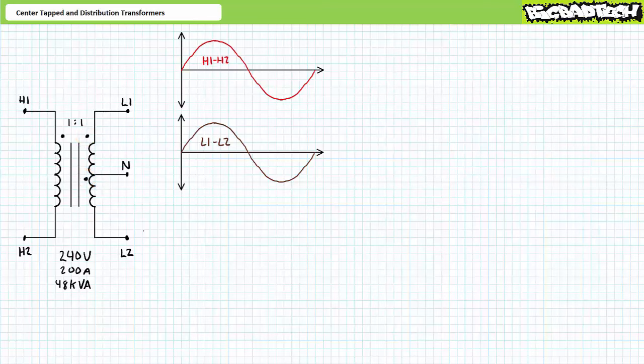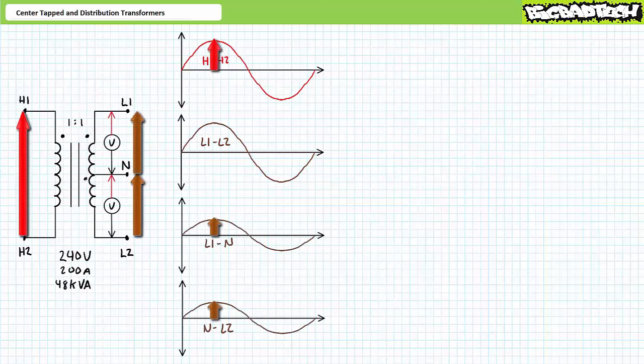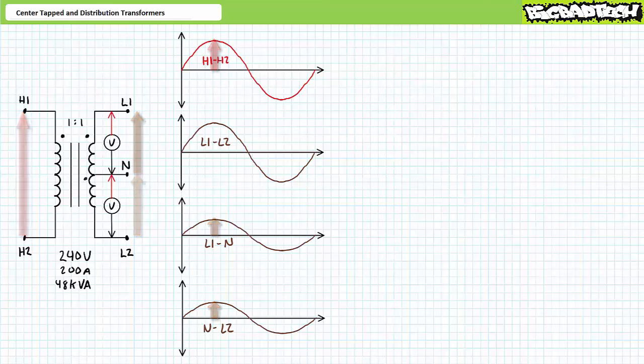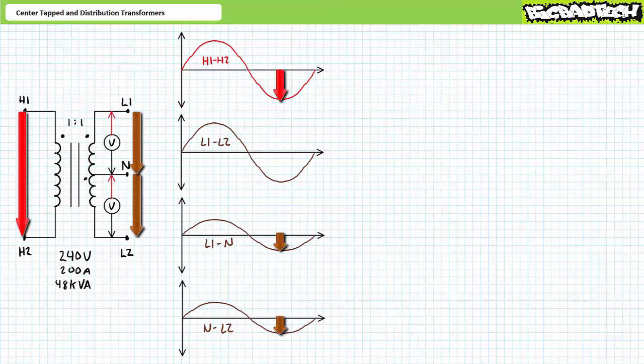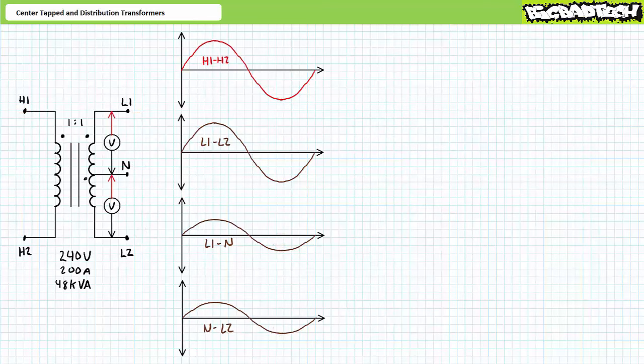Keep in mind the system is presently floating with no reference to ground. When H1 to H2 peaks positively, a voltmeter placed positive-negative L1 to N would also peak positively, as would a voltmeter placed positive-negative N to L2. Similarly, when H1 to H2 valleys negatively, a voltmeter placed positive-negative L1 to N would valley negatively, as would a voltmeter placed positive-negative N to L2.